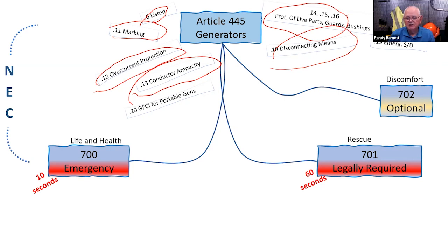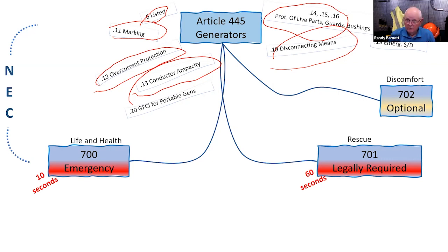Disconnecting means — I've got to have a disconnect on my generator. I have to have a way to disconnect those conductors somewhere between where I tap off the generator and where I head out to the load. It might be a disconnect switch or a breaker. That disconnect can be located internal to the structure where the generator is housed, so I would open a door, go into the room, and operate the disconnect. Those are really the basic requirements for Article 445 on generators — only a couple of pages long, but with good information.